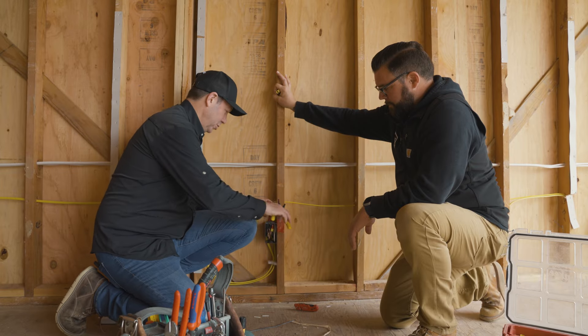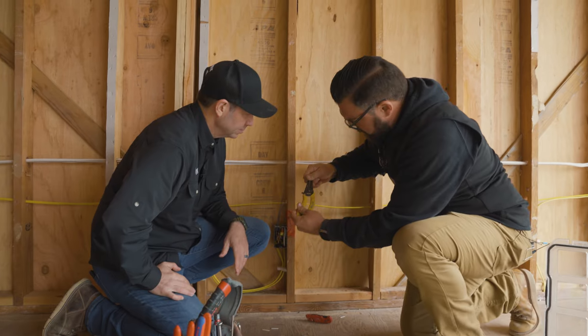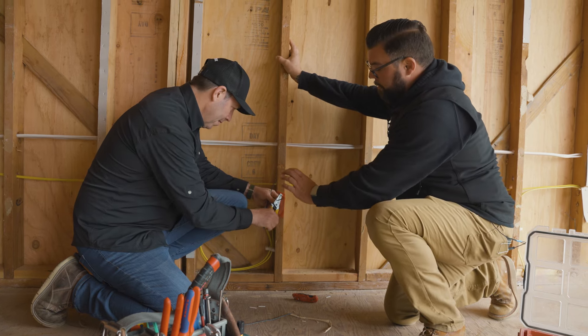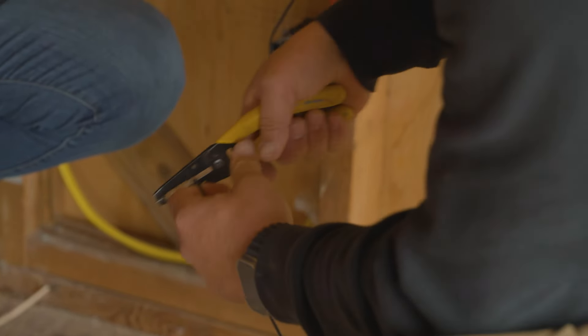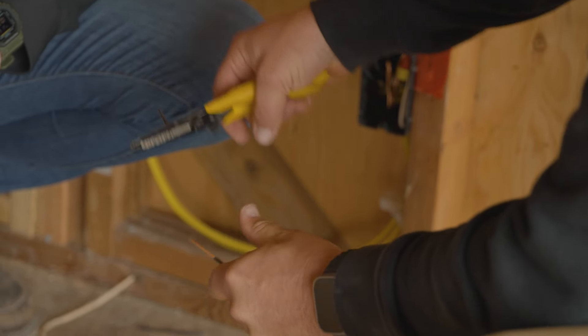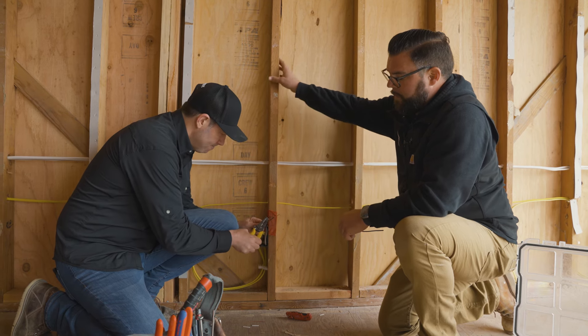When I first started 20 years ago, you build your fingertip calluses up pretty quickly. It's all working with your hands — it's trades, man. Now on the wire stripper, is there a guide that tells me which hole I need to strip with? You're going to be on the bottom two holes for 12-gauge. Squeeze it and then pull straight — don't do the twist. If you turn it, look — I just fractured that wire. It's really easy to do, but pull straight off with a nice set of strippers because otherwise you put a ding in the wire, which is a fracture point.